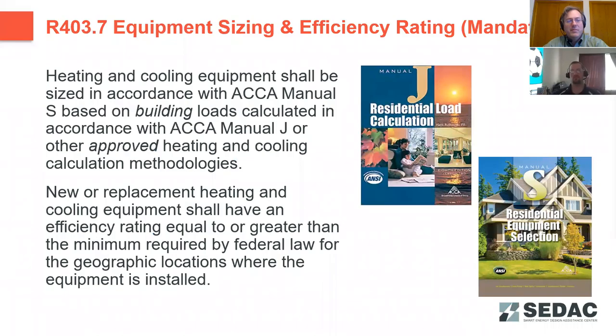How do you do that? For residential buildings, ACCA has produced the Manual J document. It is the sizing procedure for determining HVAC loads in your house based on the envelope, insulation levels, fenestration, and air leakage. They do have a handy quick calculator online that you can use to do these calculations. And then to size the equipment and install it after you've got a load calculation, you would use the ACCA ANSI Manual S. You input your load calculations into this. It accounts for equipment efficiencies and distribution efficiencies, and gives you what you should size your equipment to meet those loads. And usually it's the next size up that matches your load calculation from the Manual J.